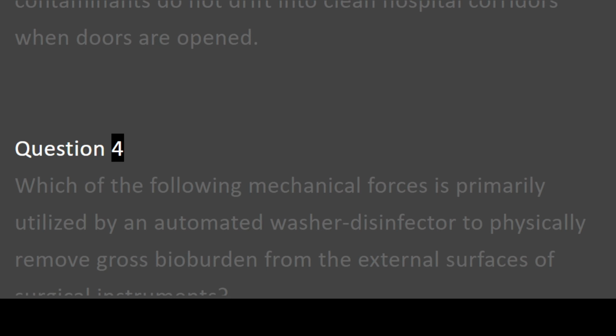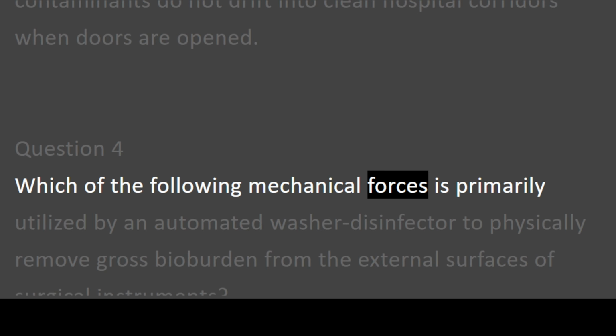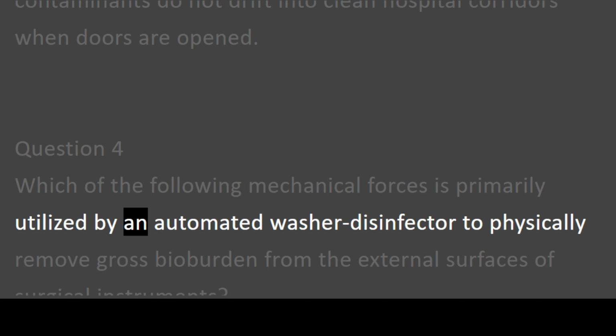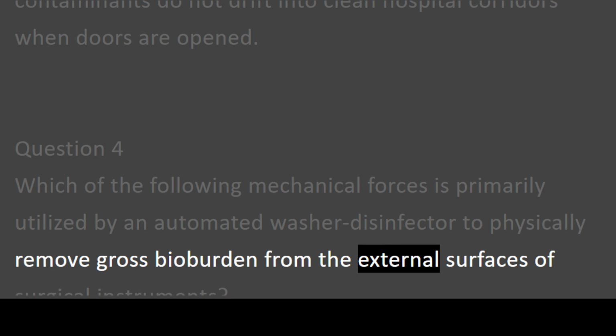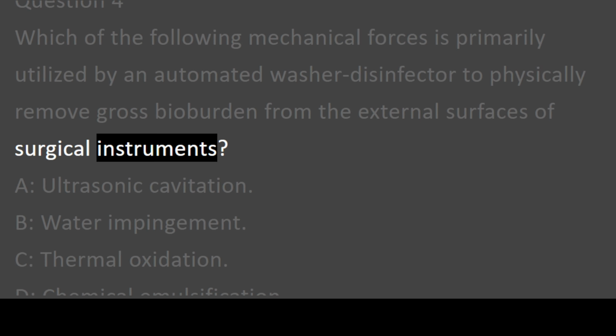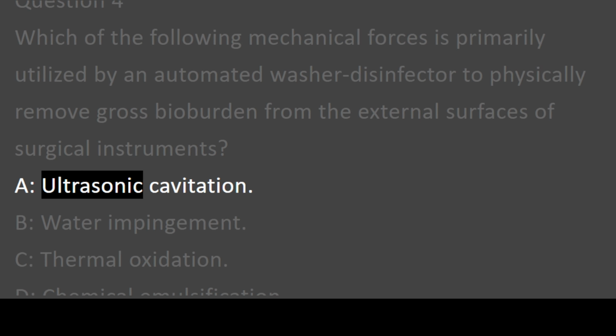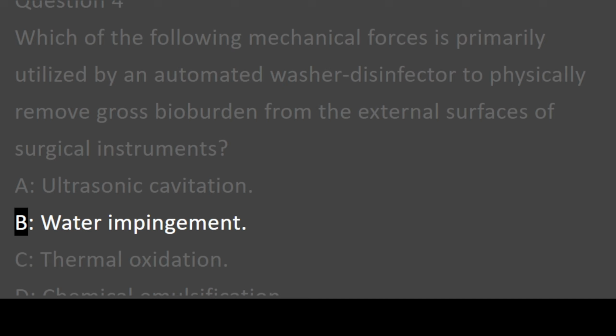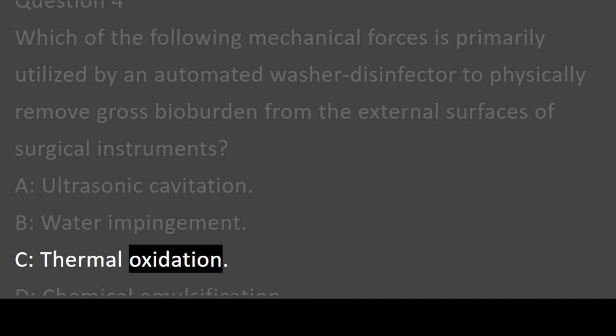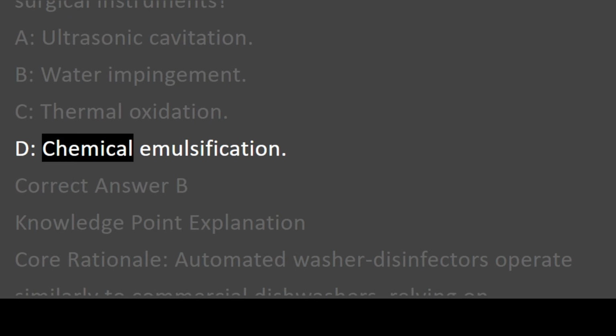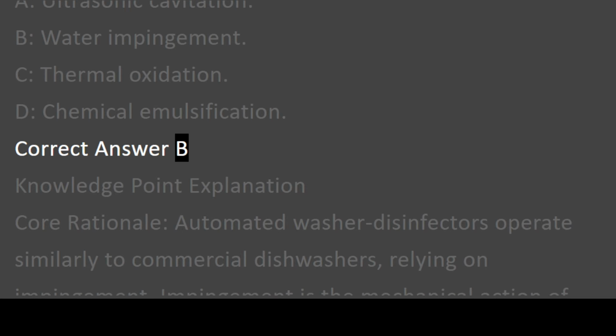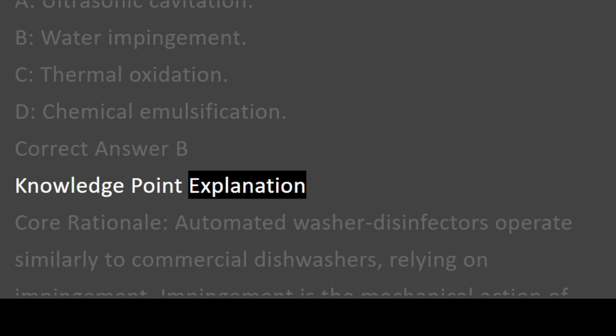Question 4. Which of the following mechanical forces is primarily utilized by an automated washer disinfector to physically remove gross bioburden from the external surfaces of surgical instruments? A. Ultrasonic cavitation. B. Water impingement. C. Thermal oxidation. D. Chemical emulsification. Correct answer B. Knowledge point explanation.